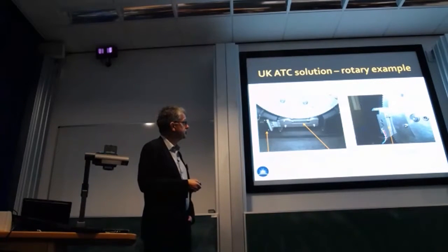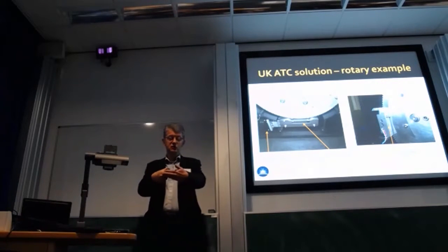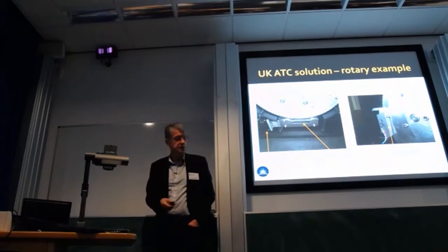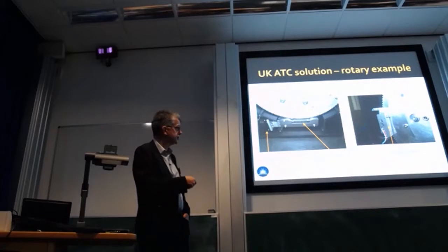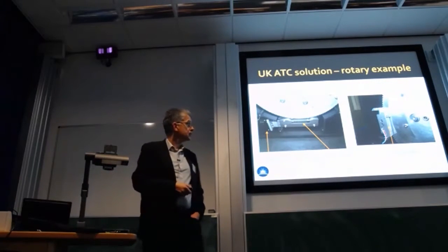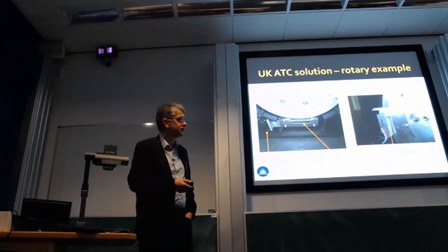And we measure the position using a simple microswitch. So we go against the datum, detect the switch changing, then move back slowly using the stepper motor until the switch switches back on again, and that gives you your datum. And then you go to positioning by using the stepper motor and counting steps, which is fine, but there's always a slight worry that you might have lost steps somewhere if you've got excess friction.